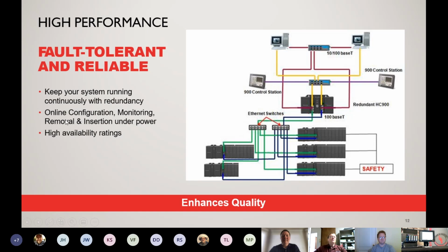Fault tolerant Ethernet: there is an option for fault tolerant Ethernet. The HC900 does have redundancy, as we talked about earlier. So if you have a system that's very critical, that needs to stay up and running, and you can't live with any downtime, these types of setups are probably perfect for those applications.